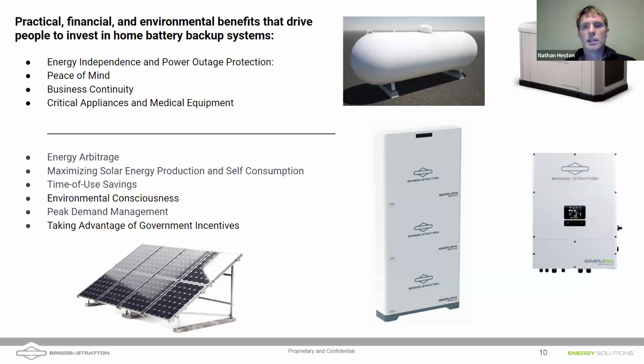So what causes our customers to want to install battery backup systems, or just backup systems in general, right? There's often a parallel made between inverters and batteries, as well as generators and fuel supply. Oftentimes that parallel is that the fuel tank is the battery, and that the engine of an ESS system is the inverter, taking the place of that generator. But that parallel breaks down as we get a little into the reasons why people are installing.